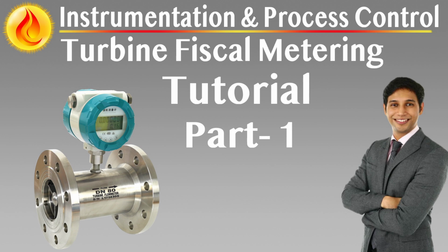Rangeability for flow dynamics. Rangeability isn't a metric, it's a design limiter and enabler. The system's maximum measurable capacity is derived from all operational meter runs at full scale, excluding standby or proving loops. The lower bound is governed by the smallest meter's precision, uncertainty at 2 sigma. System rangeability is a critical parameter specified in the project requisition and is directly linked to metering uncertainty and fiscal compliance. The inclusion of multiple parallel streams, e.g., 3 times 50% or 2 times 100%, not only supports turndown flexibility, but also satisfies minimum rangeability requirements without sacrificing resolution or control performance.